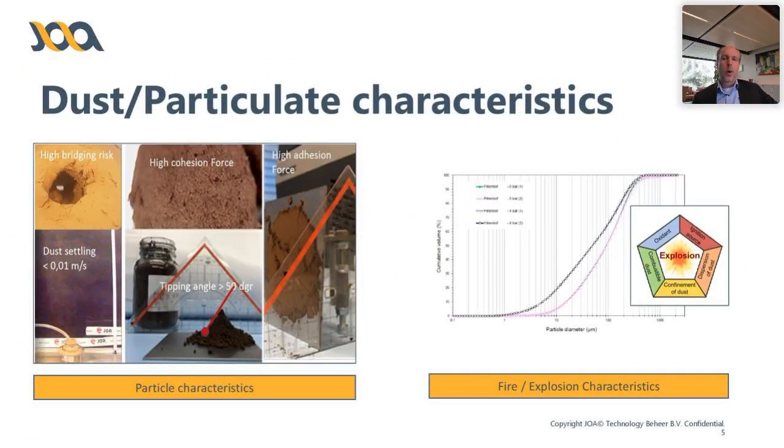And of course, what are we extracting? What can we expect from your process? What type of dust do we have to handle? For example, hygroscopic dust, which might mean that we have to maintain the relative humidity in your systems below 40 or 50%, for example. How is the product behaving inside the pipes and inside the filters?